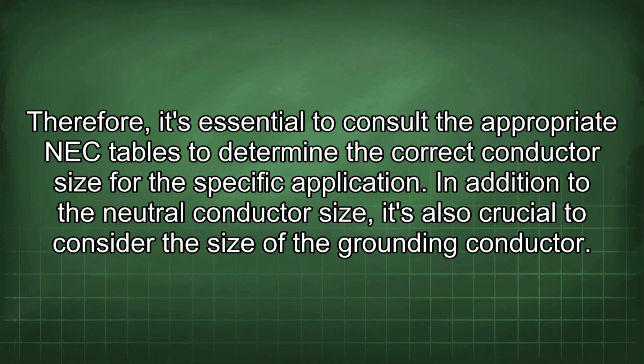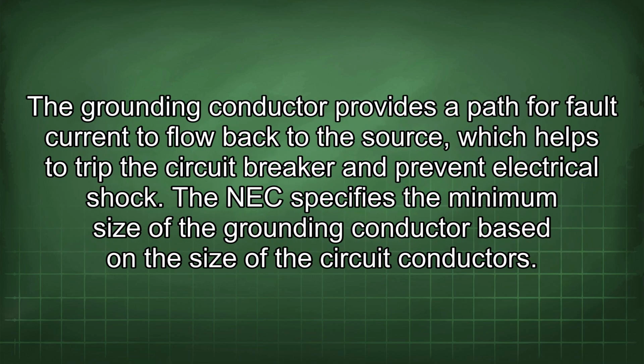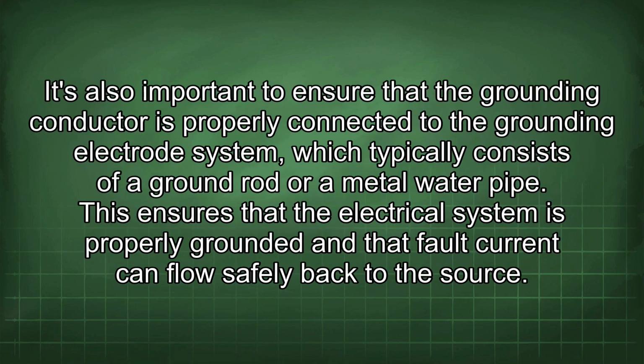In addition to the neutral conductor size, it's also crucial to consider the size of the grounding conductor. The grounding conductor provides a path for fault current to flow back to the source, which helps to trip the circuit breaker and prevent electrical shock. The NEC specifies the minimum size of the grounding conductor based on the size of the circuit conductors. It's also important to ensure that the grounding conductor is properly connected to the grounding electrode system, which typically consists of a ground rod or metal water pipe. This ensures that the electrical system is properly grounded and that fault current can flow safely back to the source.